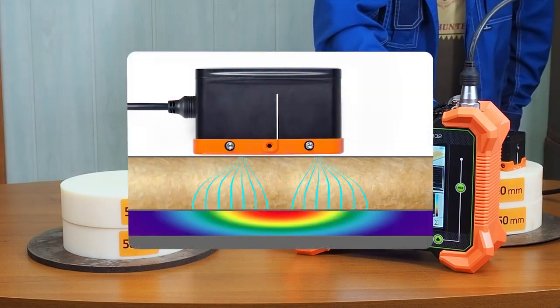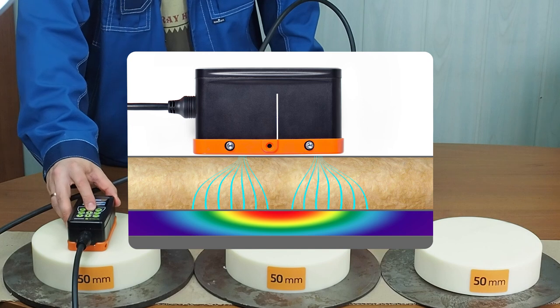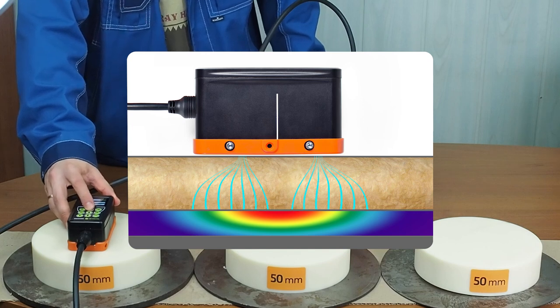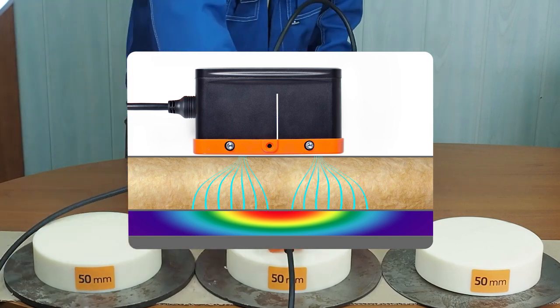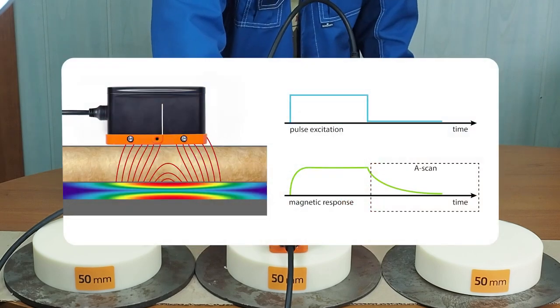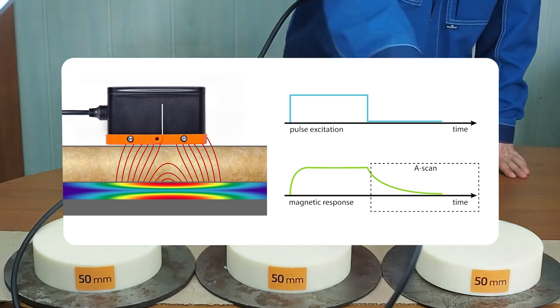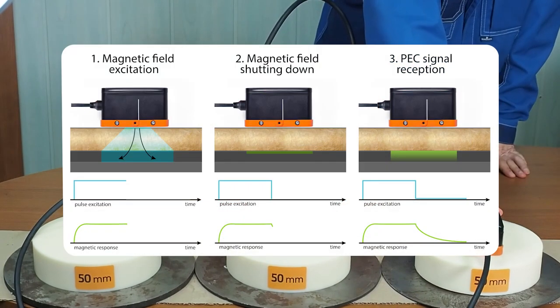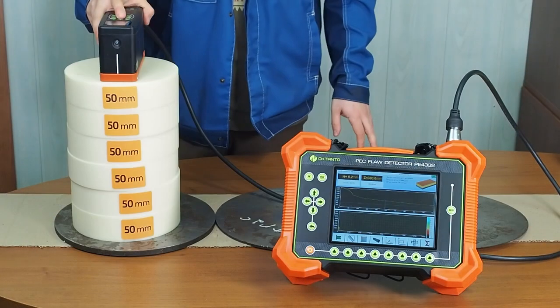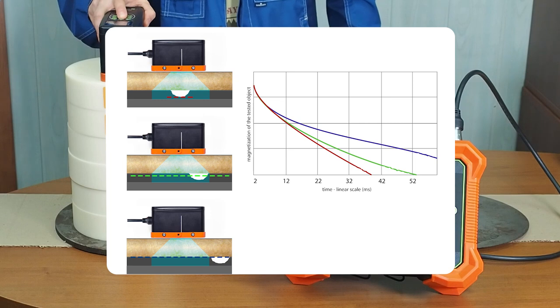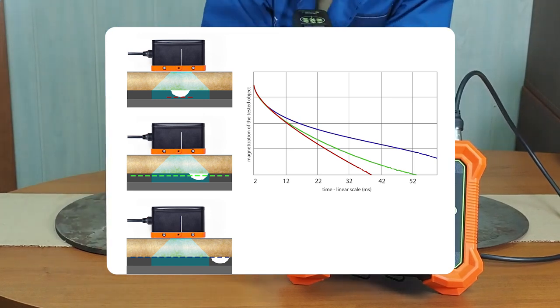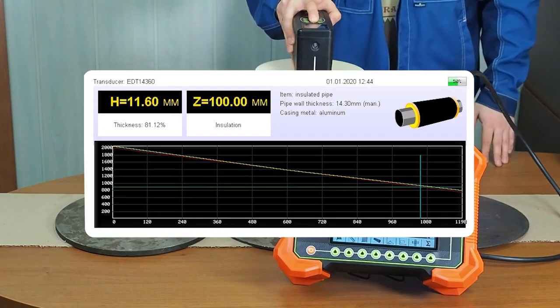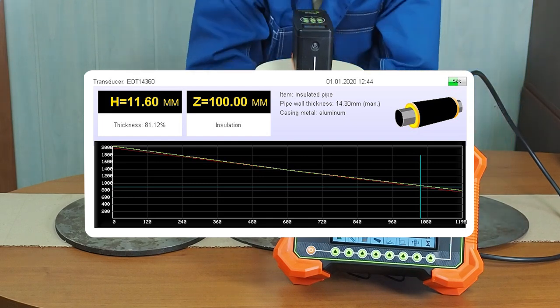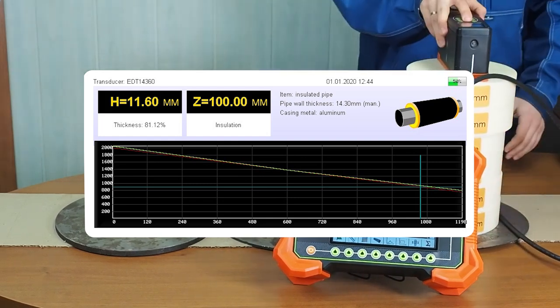The measurements begin by applying a sufficiently long current pulse to the sensor coil. This current generates a magnetic field that completely magnetizes the test object. When the current is interrupted, eddy currents arise in the test object, preventing demagnetization of the object. The thicker the metal under the sensor, the longer the demagnetization of such object. Thus, the method is based on dependence of the test object demagnetization rate on the object thickness.